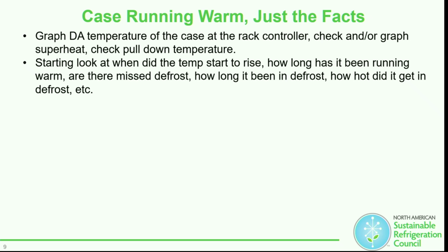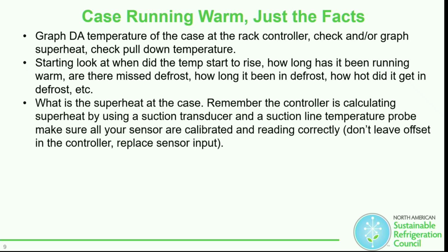Check if they're missing the defrost, how long it's actually been in defrost, and how hot it actually got in the defrost. Usually we have it on a time, right? And in some of the case controllers, because we deal with 20 different manufacturers, it could also be a demand defrost. What's the superheat of the case? Remember, the controller is calculating the superheat using the suction pressure transducer and the suction line temperature probe.